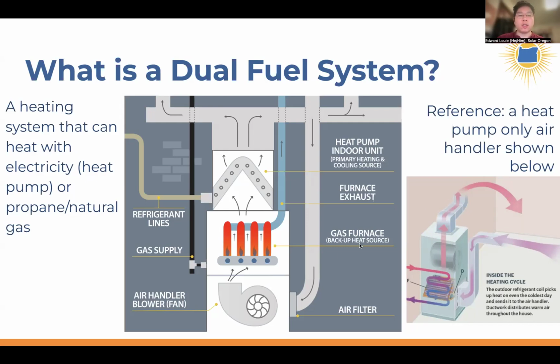So, a dual fuel heat pump system is one where you have a traditional gas furnace, which consists of typically a blower at the bottom and then a heat exchanger, where the natural gas or propane combustion happens to be able to produce heat. And then you have a coil sitting on top of it, and this coil is connected to an outdoor unit that has a reversing valve, and that reversing valve allows this coil to operate in cooling mode or air conditioning mode during the summertime, and then it can also operate in heating mode in the wintertime. And so at any point in time, the system only operates in heat pump mode or gas mode.